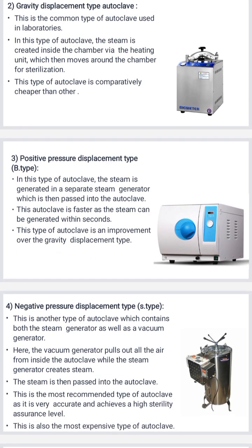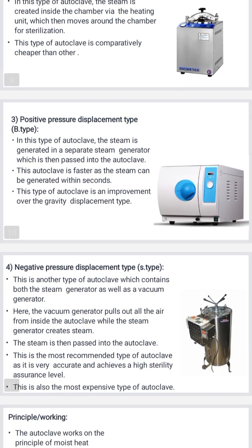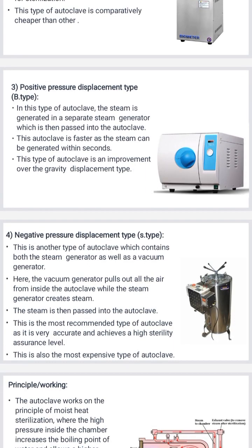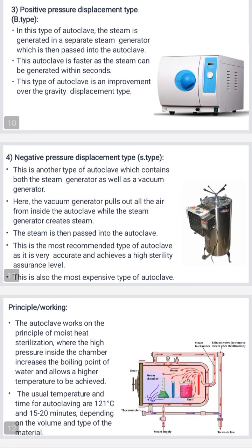The fourth type is the negative pressure displacement type, or S type. This is another type of autoclave which contains both the steam generator as well as a vacuum generator. Here the vacuum generator pulls out all the air from inside the autoclave while the steam generator creates steam. The steam is then passed into the autoclave. This is the most recommended type of autoclave. It is very efficient and achieves a high sterility assurance level. This is also the most expensive type of autoclave.